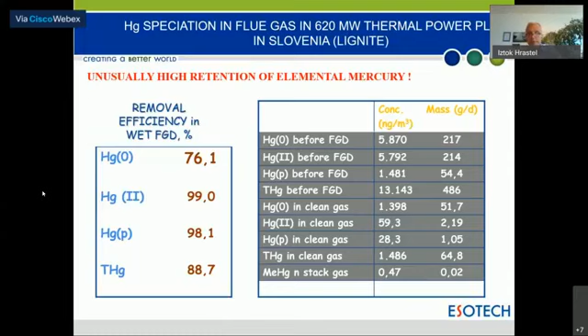Consequently, emission standards are becoming more and more stringent, from 50 micrograms per cubic meter a few years ago, going down to as low as 1 microgram per cubic meter. In flue gases, mercury appears in different chemical species: elemental, oxidized, and particle-bound mercury. Oxidized and particle-bound mercury are soluble in water solution, while elemental mercury is only slightly soluble. This results in the fact that the majority of elemental mercury passes through the wet FGD process and goes to the atmosphere.